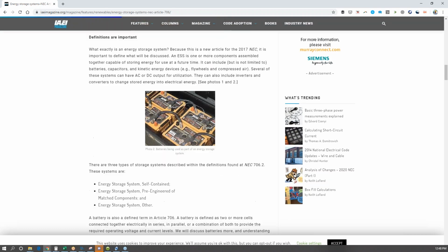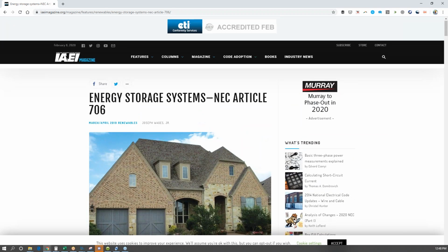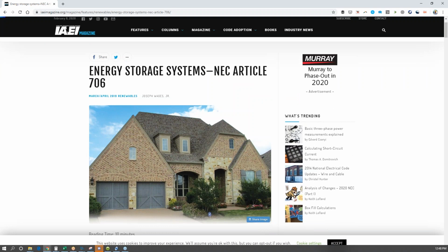So, National Electric Code is looking at a couple of different aspects. One is the ability to ventilate the room and not having other explosive materials like gas lines in that room. The second is mechanical protection, and the mechanical protection requirements increase when you get into higher voltage systems. Things like the means of egress out of the room, which way the door opens, is all governed by code.